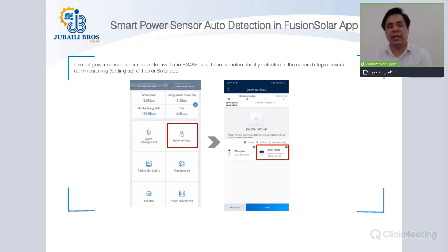That will take you to the quick setting of the PV plant. So the first thing that you will do is that under the quick setting, you will scan one of the inverters or the dongles. Once that is done, the next components within that PV plant will be automatically detected. So if you have a smart power sensor in that PV plant, which is connected to this inverter and dongle, that will be automatically detected.